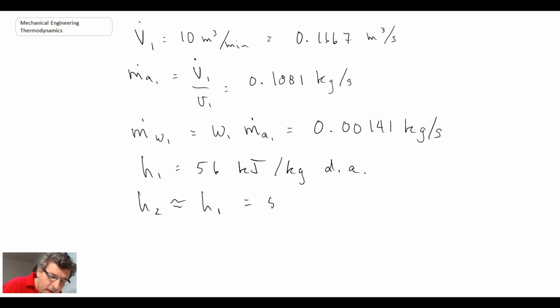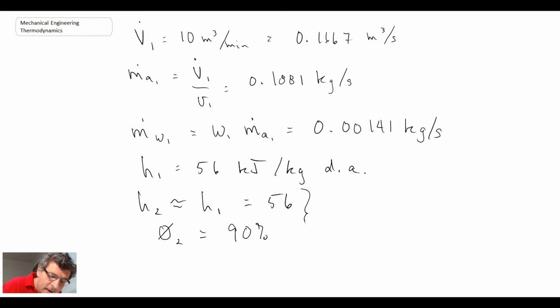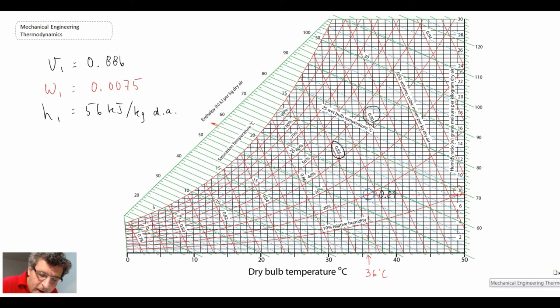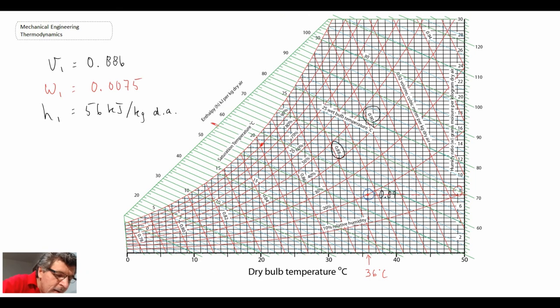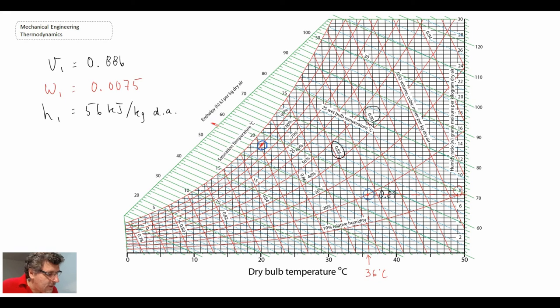Since H2 equals H1 for an evaporative cooler, H2 is also 56 kJ/kg dry air. We know the relative humidity at state two is 90%. Following the constant enthalpy line upward on the psychrometric chart until it intersects the 90% relative humidity curve gives us state two, which we circle in blue.